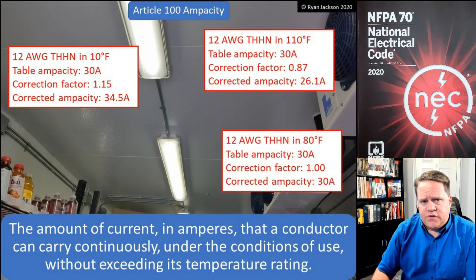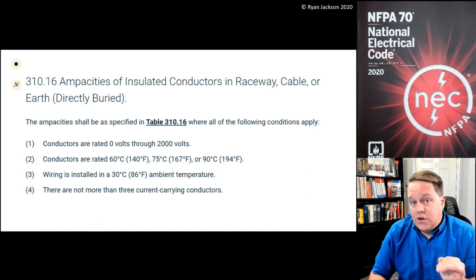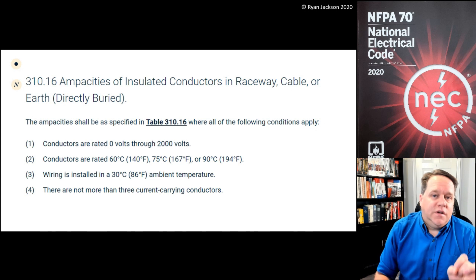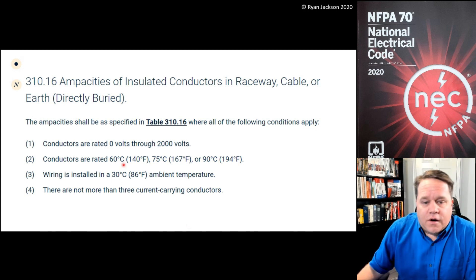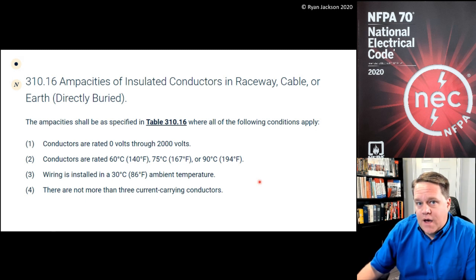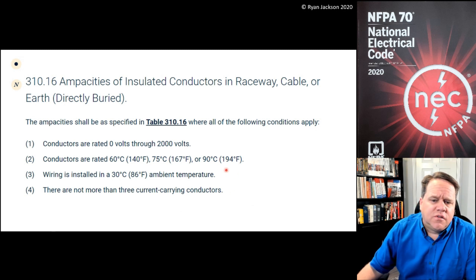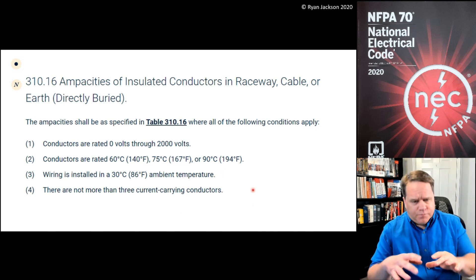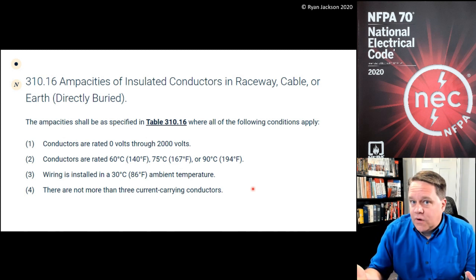Under the conditions of use — what are the conditions of use? If we look at section 310.16, it tells us the conditions of use that the ampacity values in table 310.16 are based on: conductors rated 0 to 2,000 volts, conductors rated 60, 75, or 90 degrees, wiring in an 86°F ambient temperature, and not more than three current-carrying conductors. It's really those last two I want to focus on — those are both conditions of use.